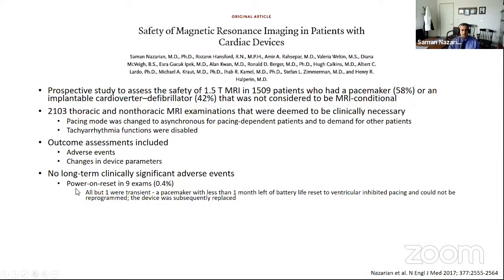Now, what happens with a power on reset? If you have a pacemaker, you'll go to ventricular inhibited mode, and the problem with that is if they're dependent, then they won't be pacing. So you're watching them, and you can pull them out and they'll start pacing. It'll be okay, but you have to make sure somebody is watching them. And then the other problem is that if it's a defibrillator, the tachycardia therapies will turn back on. Now, it's not going to shock the patient, because the transformer won't work in the magnet. It won't actually be able to charge up to voltage and deliver the shock. But that can then lead to a worse problem with the generator and drain the battery completely. So it's better not to do the exam if they're really getting close to the elective replacement interval of the battery. But for the most part, this is very rare.